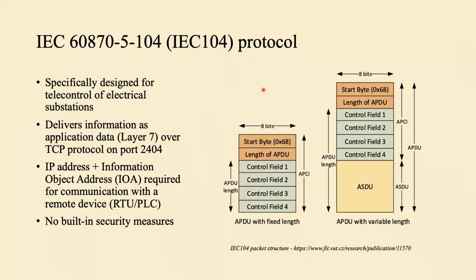So there are two types of packets for the protocol. One on the left side is just a fixed length packet. So you have two start bytes, and then control fields, which is not that interesting from a security perspective. But then on the right side you have a variable length packet, and this bit right here is called an ASDU, or Application Service Data Unit, which carries the actual information to and from the RTU.